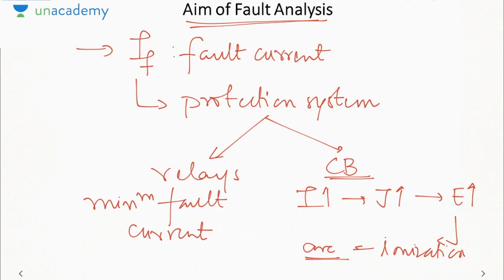So whenever the circuit breaker will try to separate, an arc will be struck between the circuit breaker contacts, and till the arc is present, there will be current conduction between the two contacts via the ionized medium, because ionized medium will act as a conductor to conduct the current between the two plates. So if you have to actually open the circuit, then you have to remove this arc.